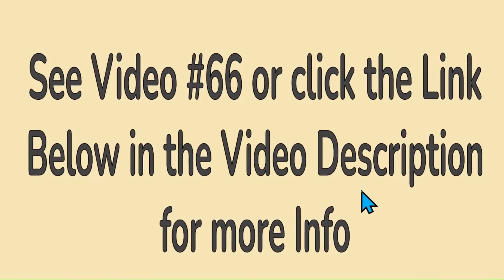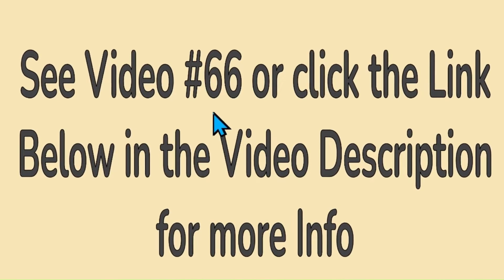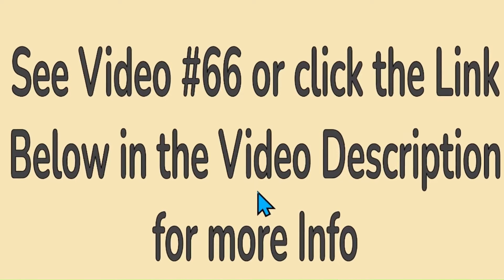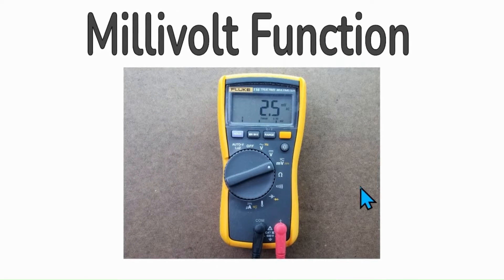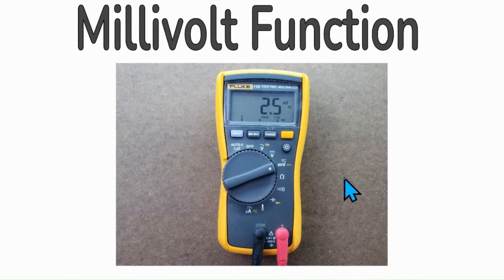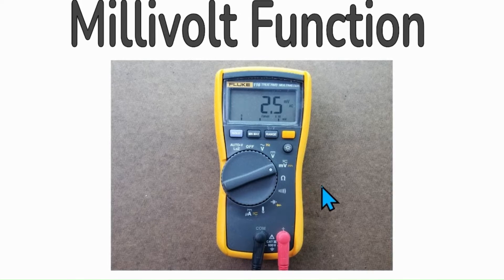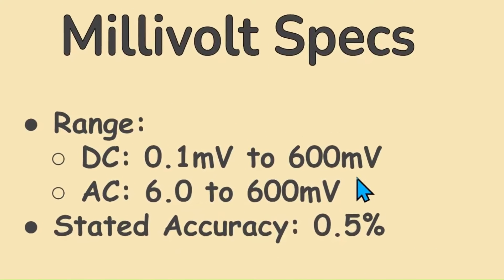For a comprehensive demonstration on how to detect voltage anomalies using Low Z, please see video number 66 on this YouTube channel, or click the link in the description for my blog on Low Z theory and usage. The millivolt function measures AC millivolts from 6.0 millivolts to 600 millivolts, and DC millivolts from 0.1 to 600 millivolts, with a stated accuracy of 0.5%. This is very handy for measuring small voltages.